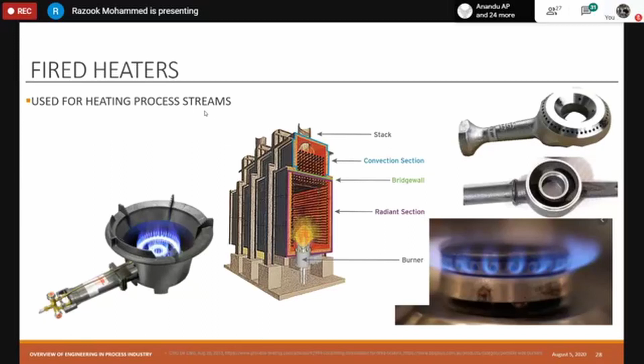These are used in process streams, for two reasons: when you have excess fuel which cannot be used anywhere, you tend to use fire heaters, or you use them when you need very high temperatures. But I have also seen fire heaters used in places where very low temperature was required, because we had excess fuel which we could not do anything with except flare it away. So instead of flaring it, we used to capture that heat, put it in a fire heater, and use it for some process heating purpose.